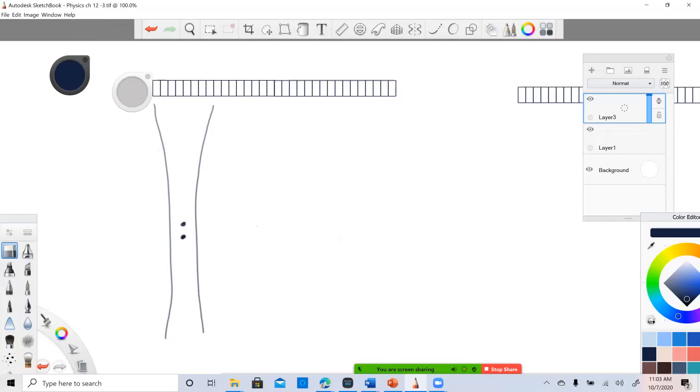Axial resolution, by the way, does not change. We have the same axial resolution up here as we do all the way down here. Even as the beam is spreading out and getting really horrible in the far zone, Fraunhofer zone, axial resolution stays the same because it's one half the length of the pulse, right? So that stays the same.